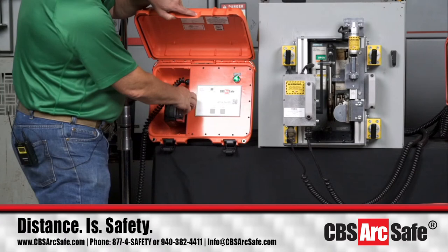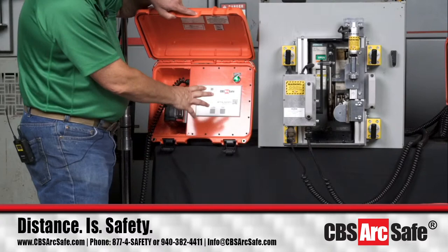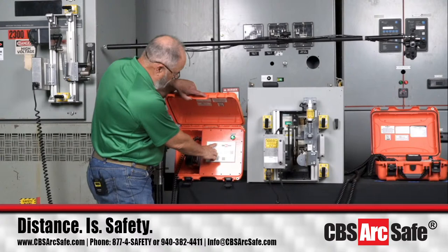If you want to turn it off and turn it back on, you're going to see the AR is going to come on in just the closed position right there. And I'm going to set it right there with that. And so the AR, the actuators that require AR, it's much easier to set up, whether it's on this one or whether it's on our RSO3, for ease of operation. So I don't need it for this actual actuator, so I'm going to put it back to off, hold it down for 5 seconds, get the green light to come on. And then now it's set for off.